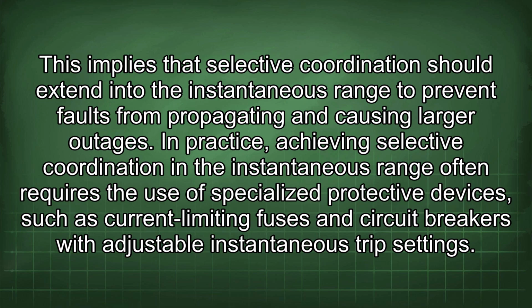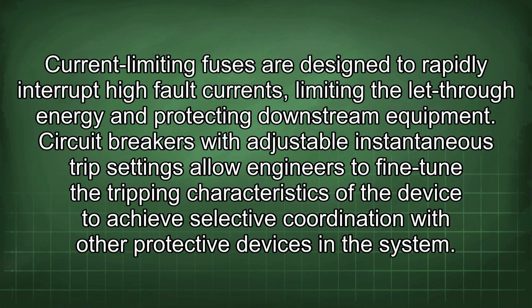In practice, achieving selective coordination in the instantaneous range often requires the use of specialized protective devices such as current-limiting fuses and circuit breakers with adjustable instantaneous trip settings. Current-limiting fuses are designed to rapidly interrupt high-fault currents, limiting their let-through energy and protecting downstream equipment. Circuit breakers with adjustable instantaneous trip settings allow engineers to fine-tune the tripping characteristics of the device to achieve selective coordination with other protective devices in the system.